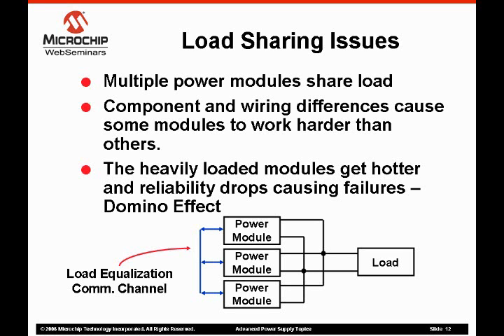Slight differences in component values and wiring resistances cause the output voltage at some modules to be slightly higher than others. Even if the voltage imbalance is only millivolts, the result is that some modules hog the load while others are lightly loaded. The heavily loaded modules run hotter and will probably fail earlier, and the remainder carry more of a load, which can start creating a domino effect.